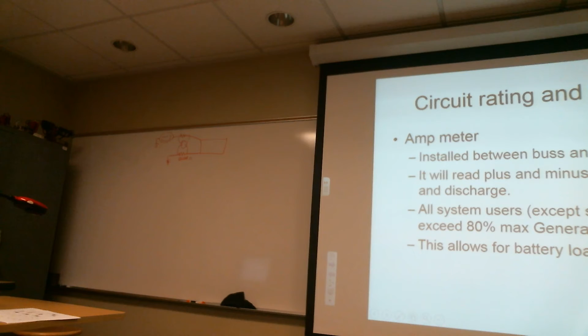Now I've got a battery or charging system, a generator, that's being tasked to put everything on, plus it's got to charge up the battery. So everything turned on can't exceed some value, and that could be different depending on the airplane. However, the FAA theorized you may overload it a little bit for a short period of time, but the battery is probably going to come back up pretty quickly just from starting. So they came up with a round number: 80%.